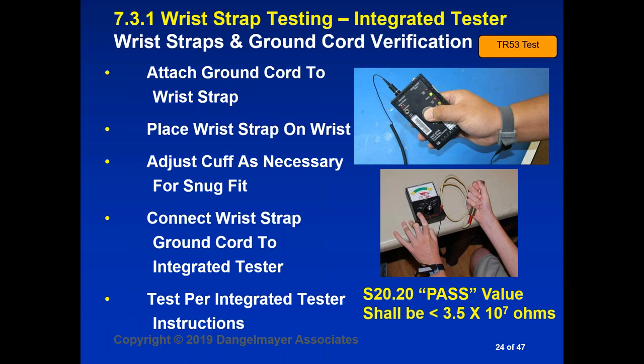If you're using an integrated tester, one of the things to verify is that it is set for the correct resistance value for measurements. The high level resistance is specified in S2020 as 3.5 times 10 to the 7th ohms, or 35 megaohms. The low resistance level is a safety factor that most wrist straps will meet, but you really want to check that they have at least a 750K resistance in the ground cord and wrist strap circuit. Usually there's a 1 megaohm resistance there. Occasionally we find there are cords that look like ground cords but are not for wrist straps, and they may not have a resistor internally. So it's a really good idea to check the low resistance measurement on the wrist strap as well.